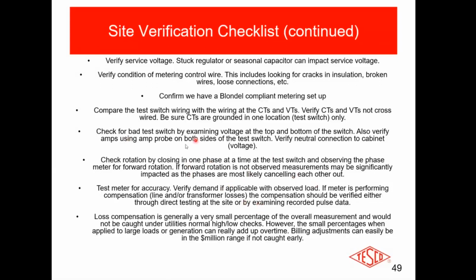On occasion, you will find a bad test switch. Of course, it wouldn't be a TESCO test switch if that were the case, but on occasion you could find a bad test switch. Suspect everything. Check everything when you go out there. Check that it is Blondel compliant. Everything may be perfect. Check and see how many watt-hour meters do we have in here? How many lines do we have? Do we have 2 for 3, or do we have 2 for 4? Okay.